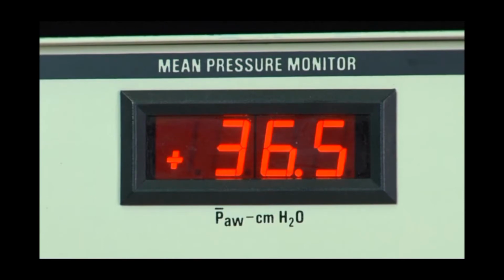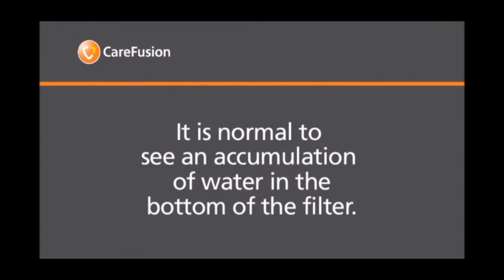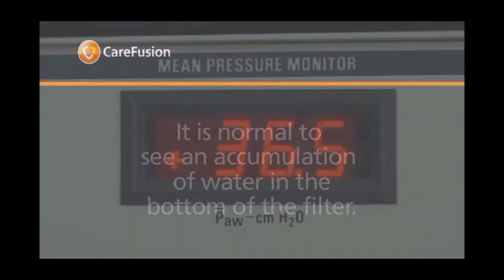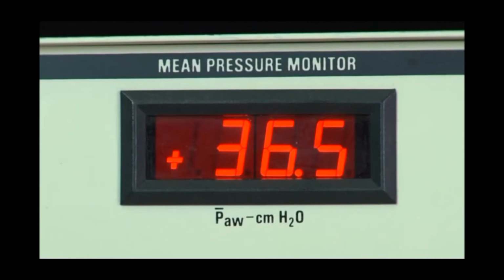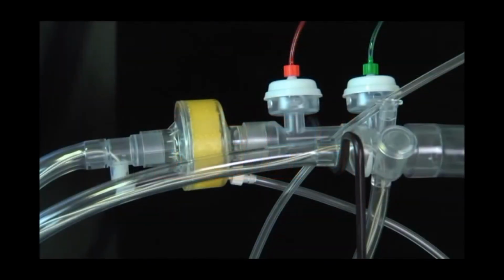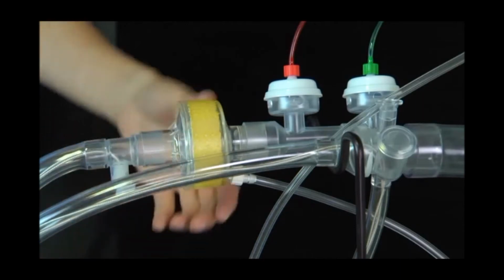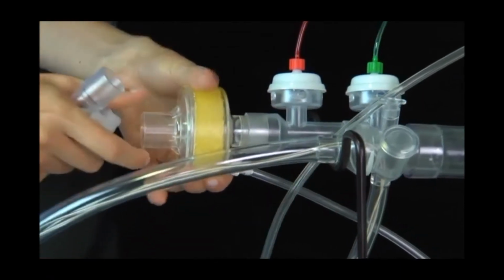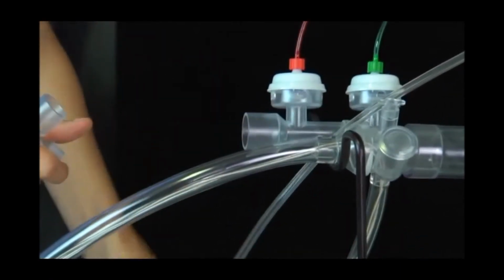Pressures will stabilize once the filter is fully wetted. Decrease the mean airway pressure or power controls accordingly. Likewise, when a used filter is replaced, pressures may be slightly higher since the new filter is dry. Readjust pressures as needed. If the expiratory filter is no longer needed, the circuit ends may be connected directly.